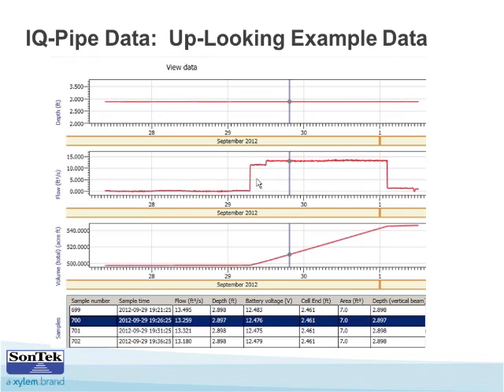Similar depth, similar flow. They turned on the pumps, and total volume started to be recorded. Flow here is 13 point something again. I think this shows SonTek has done their homework - it doesn't matter whether the instrument is top looking down or bottom looking up. Under the same flow conditions, you get the same flow number. It really validates itself, especially since they were mounted just about 100 feet apart from each other.